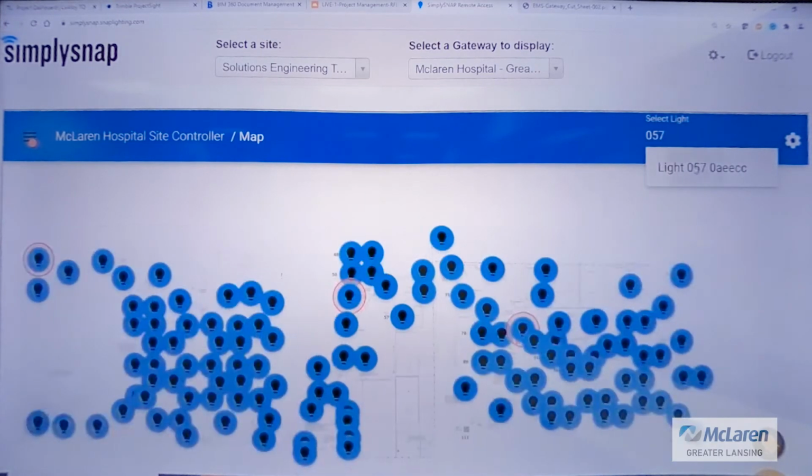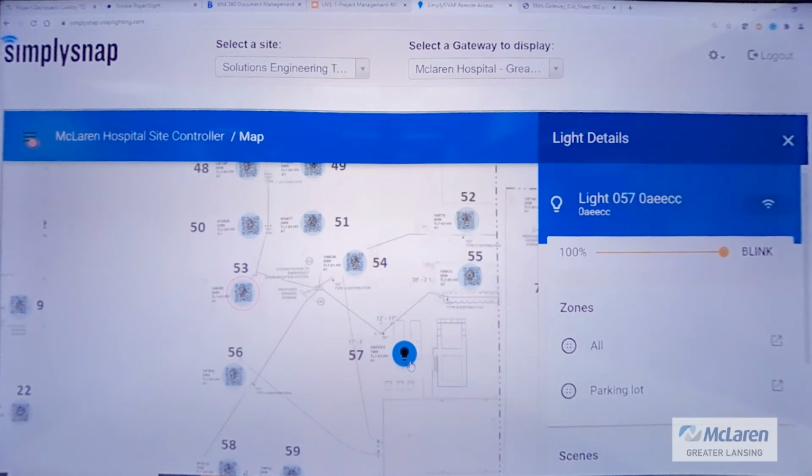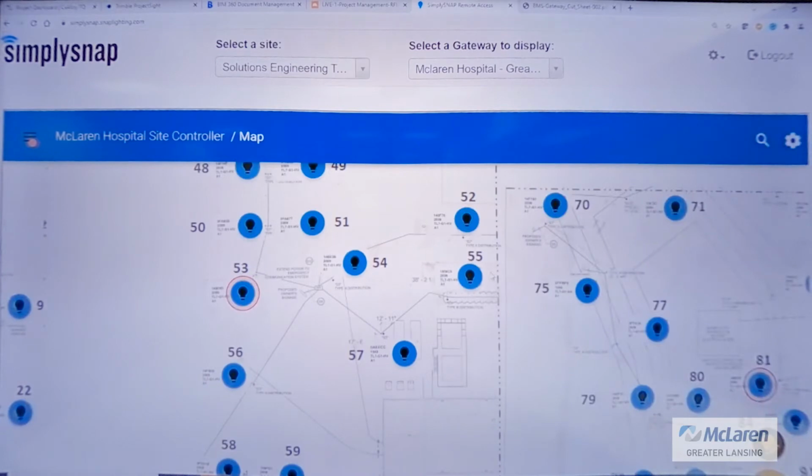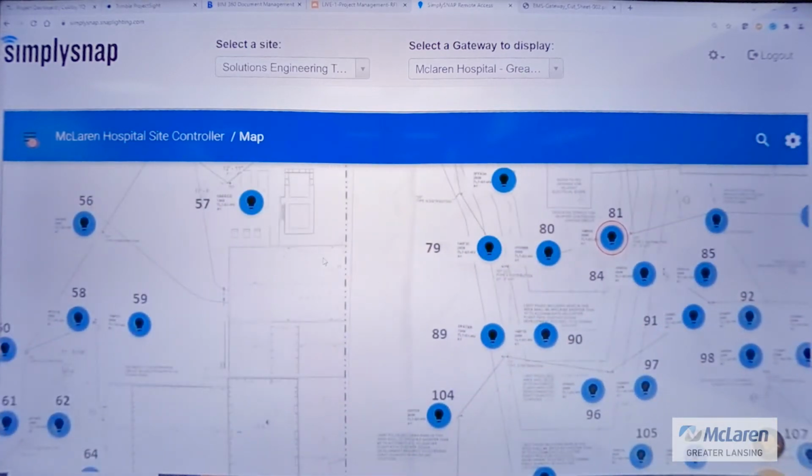So the loading dock over there has a pole that has a light on it, and the photocell on that particular controller is the one that's being used to detect darkness. But yeah, we could set up any other photocell to be used as a backup. It wouldn't directly use that backup. Say for whatever reason that particular pole gets powered down and we can't detect anything from that sensor, then the lights would default to not having communication to that light and just default to on at that point.